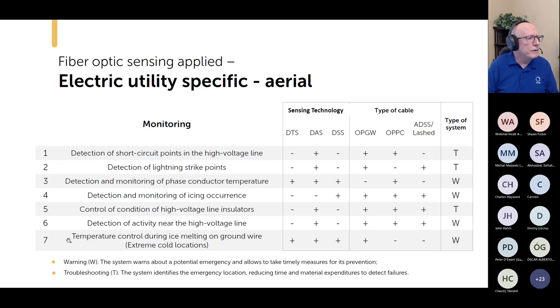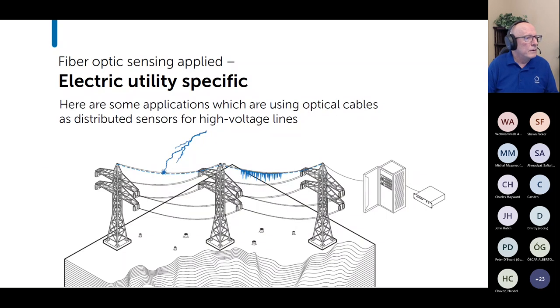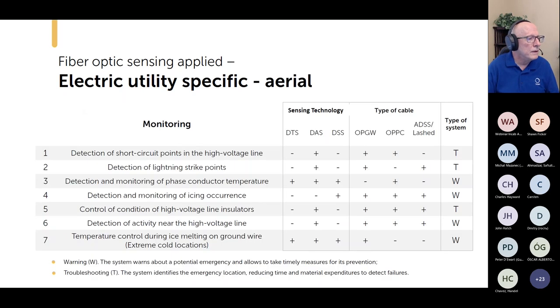And then there are some locations where you monitor the temperature with your OPGW, and you can monitor strain on your OPGW, and when ice accumulates past a point that's potentially dangerous, you can then run DC current through your OPGW to shed the ice. The sensing first of all has allowed you to detect that an unsafe condition exists. And then the temperature control allows you to know when you've shed the ice and you can turn off that circulating current. And by the way, that could be done with phase conductors as well. The fact that you could do that with OPPC or OPGW means that you can prevent cascading failures like I talked about before.